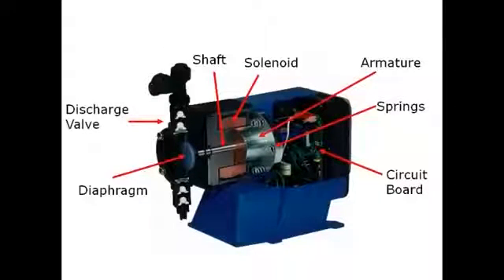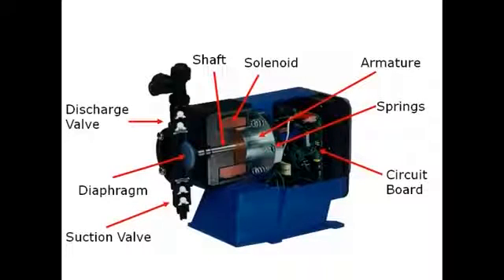When the solenoid is de-energized by the circuit board, the magnetic field collapses. The diaphragm and the armature return to the original position under the force of the springs. This action draws the fluid into the suction valve, and the cycle repeats.